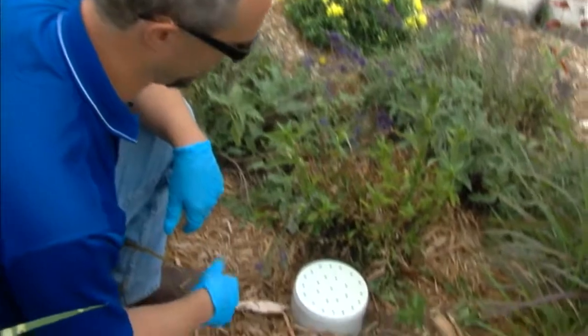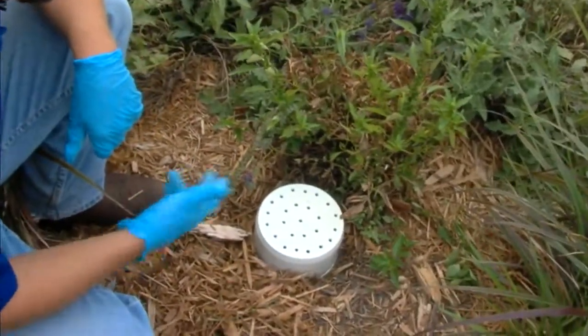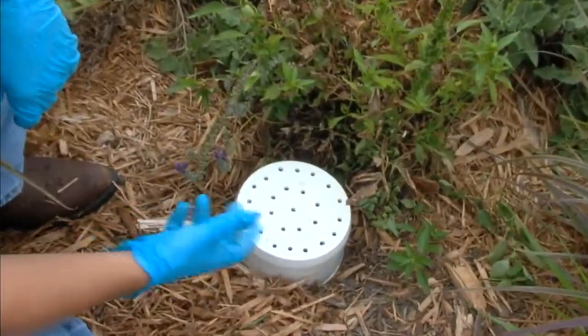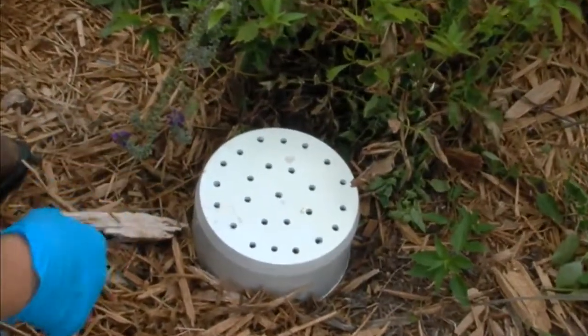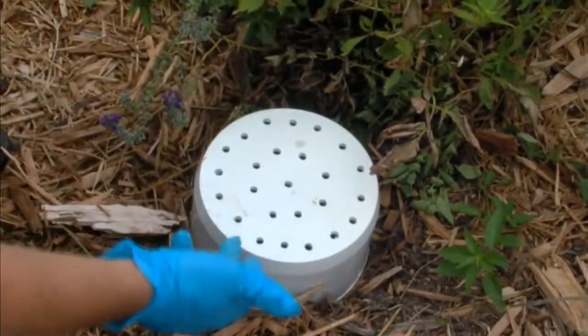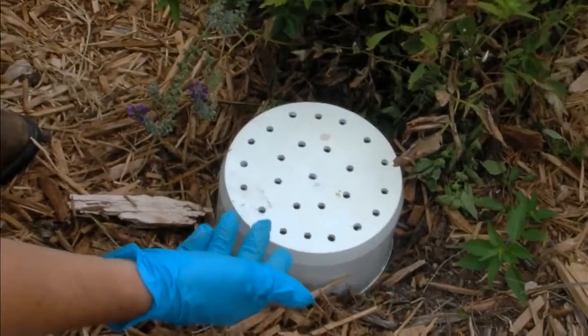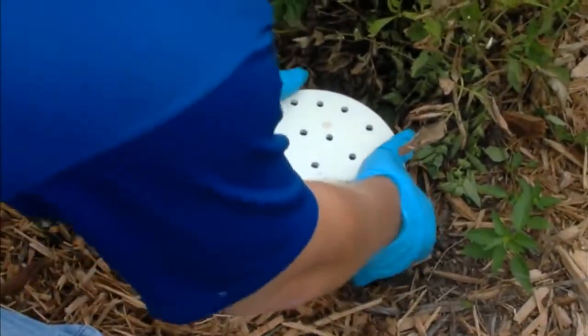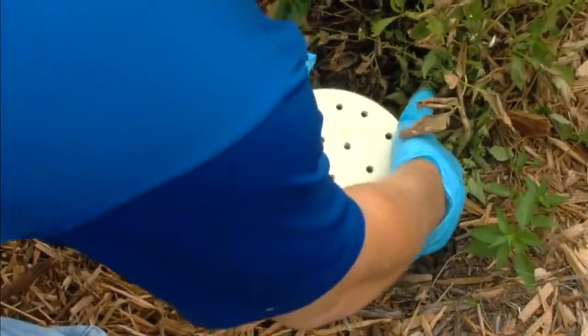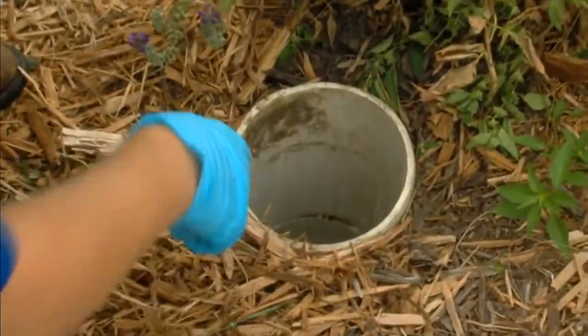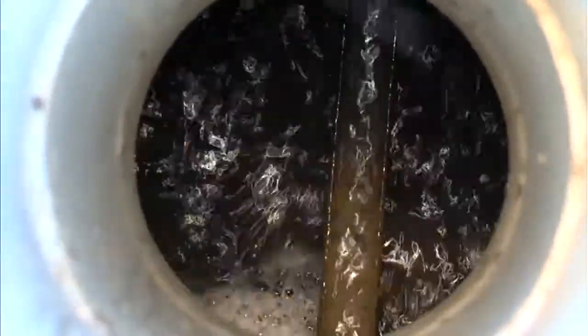Next, we're going to look at the vent and the turbulence inside the FAST system. So the 6-inch inspection riser that comes up off the FAST lid inside the FAST compartment is right here. It has a lot of holes drilled in it for a vent in this circumstance. We're going to take that cover off and then take a look down the 6-inch inspection port into the FAST system. I should see the recirculation trough of the FAST unit coming off the airlift. I do. And I should see a lot of turbulence from the airlift splashing the water over the media. And that looks good in this circumstance.